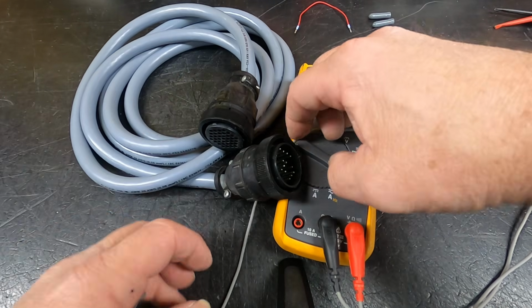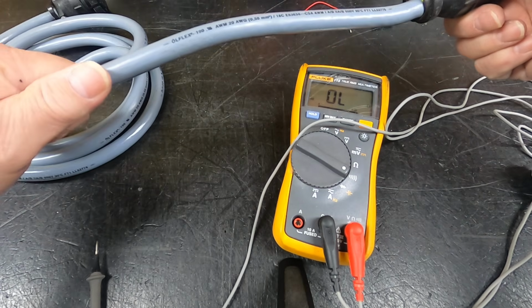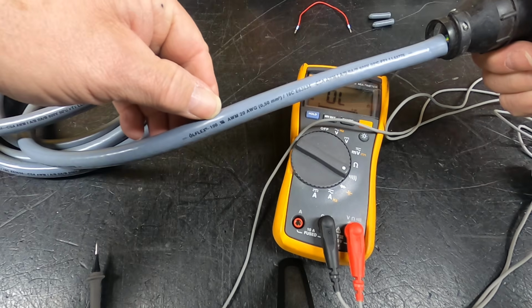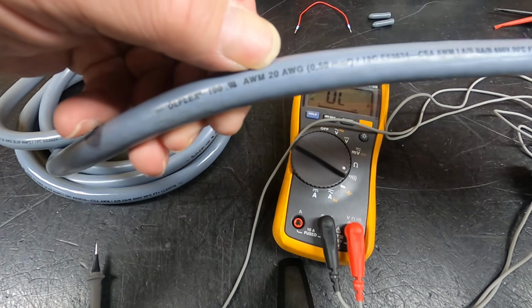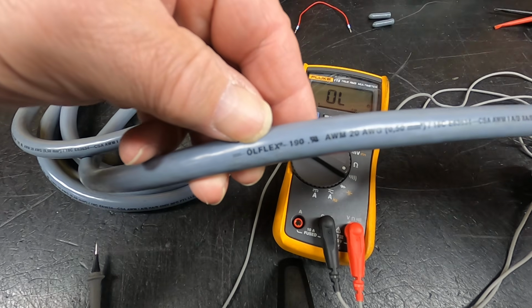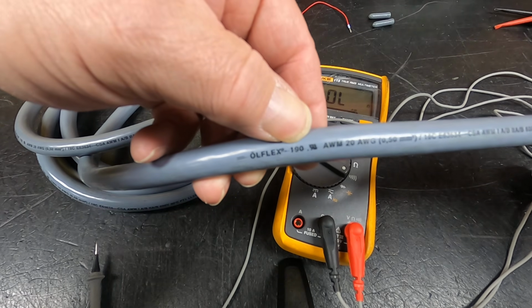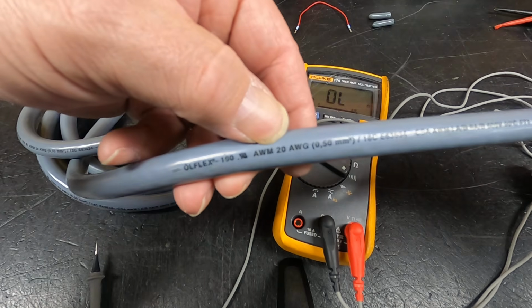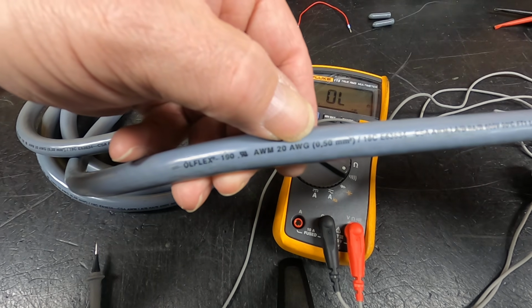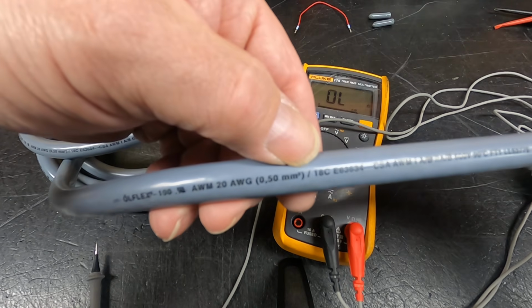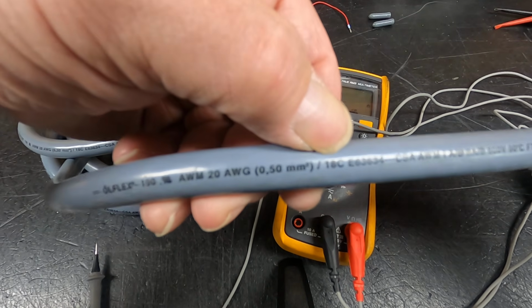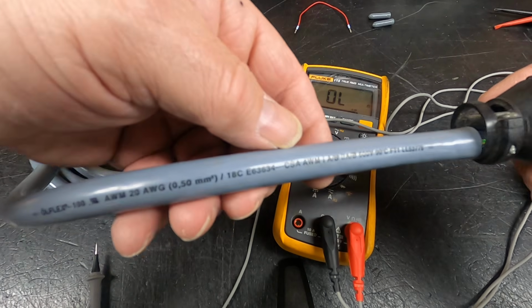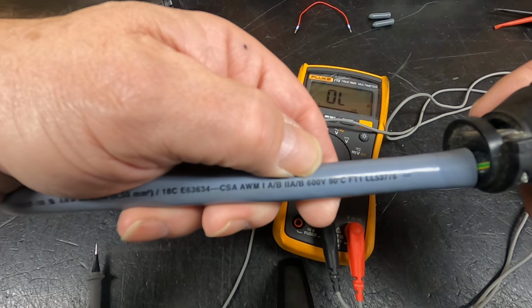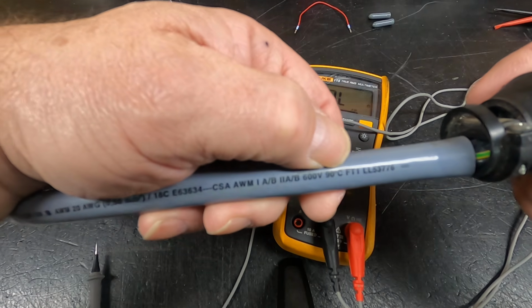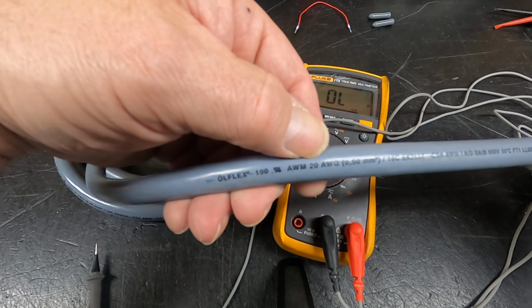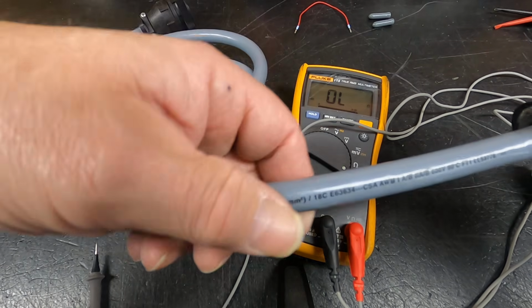For more information, when you read on the side of the cable, if I look really close, it says this cable is made by a company called ÖLFLEX, which is probably the model number or series. It is 20 gauge AWG, American wire gauge, and it has 18 conductors in it, 18C. The rest is like Canadian approvals, max voltage 600 volts, max temperature 90 degrees C, and a bunch of other stuff. But the key ones are, it's 20 gauge and it's got 18 conductors in it.